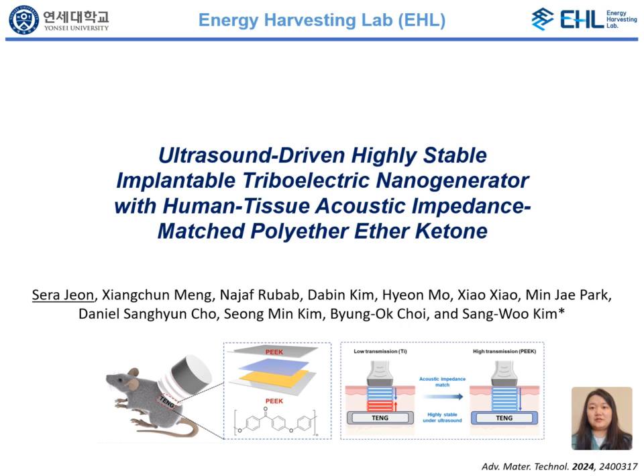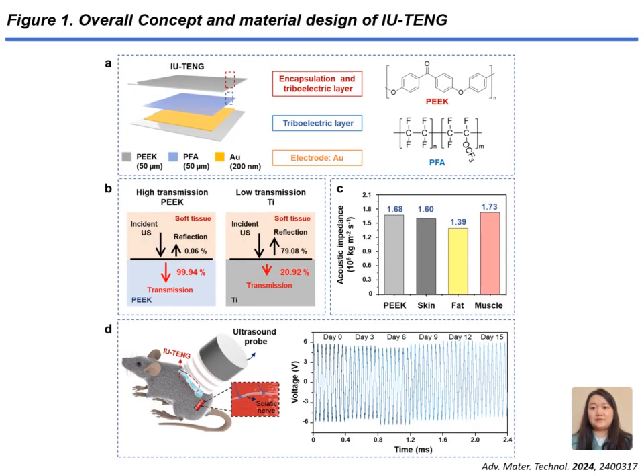Now, let's dive into the details, figure by figure. Figure 1 shows the design of the TENG. At the core is polyether ether ketone, PEEK, used for both the triboelectric and encapsulation layers. We chose PEEK for its biocompatibility, mechanical strength, and acoustic impedance that closely matches human tissues. This allows ultrasound waves to pass through the body with minimal energy loss. PEEK transmits 99.94% of the ultrasound energy, whereas materials like titanium reflect much of it, reducing power generation efficiency.